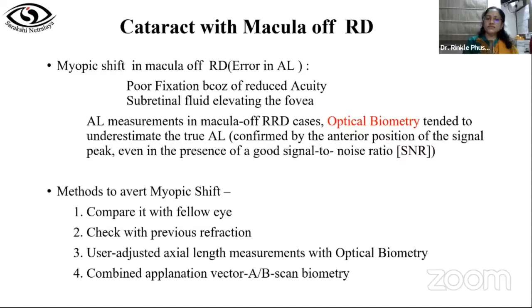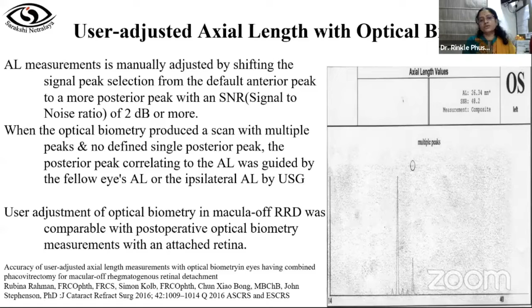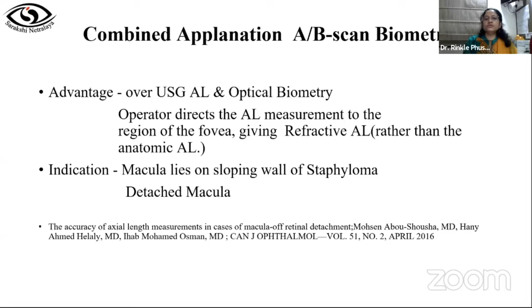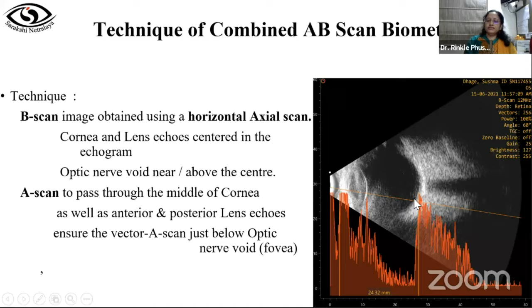One option would be to use optical biometry with user-adjusted axial length, where manually the point taken is the posterior spike, because the anterior spike is due to the detached retina. So go for the posterior spike here. Combined AB scan biometry is very useful in cases of detached macula as well as in staphyloma. So how do you do this combined AB scan biometry? You take a horizontal axial scan on B scan, put your A scan vector on the machine, and then pass the vector through the center of the cornea and the lens to the point just beneath the optic nerve void here.